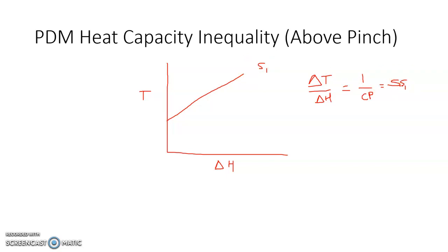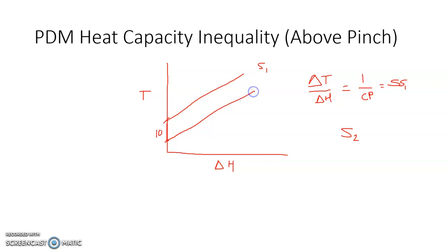Now if we have another stream S2 receiving energy from S1, S2 will be at a lower temperature. If S2 has the same CP as S1, its slope is the same and the two lines are parallel. The vertical difference — delta T minimum of 10 degrees — remains constant throughout the heat exchange. There is no problem in this case.